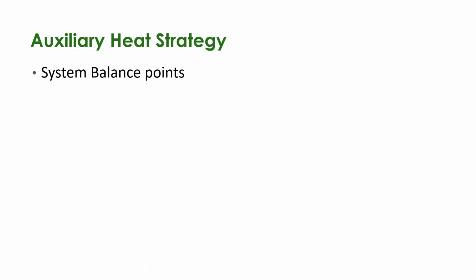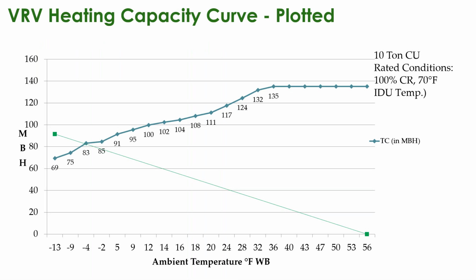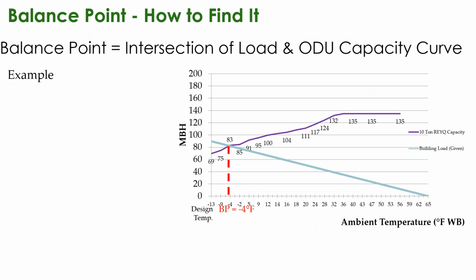So how do we decide where the best points are to apply auxiliary heat? First, you have to look at balance points for that system to your design profile. Now, every manufacturer has capacity curves published. You need to know your manufacturer, because some of them derate the outdoor unit, some of them derate the indoor unit, but you should be able to get the information to plot your load profile against the actual capacity capability of that system at your design condition. Once you have that information, you can run that to see where your balance point is.